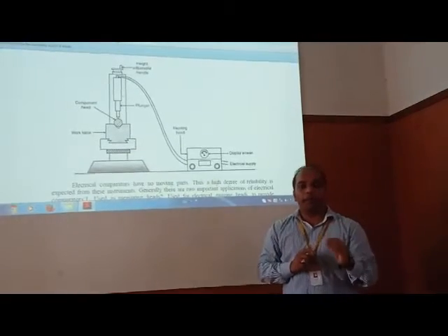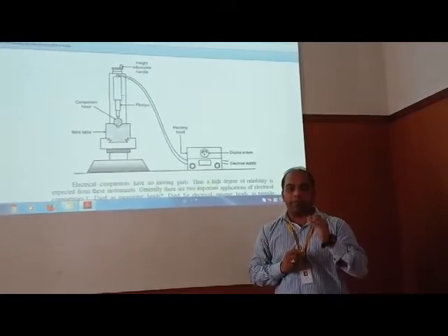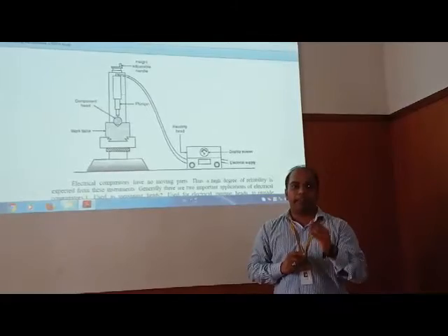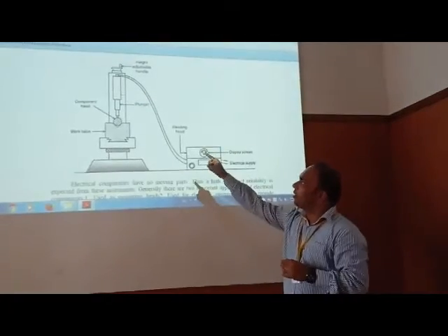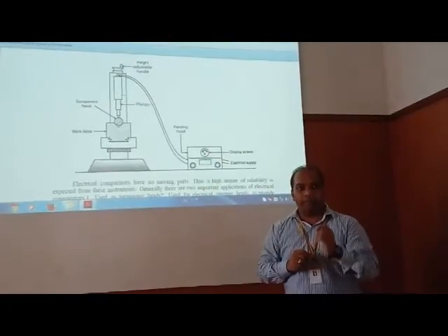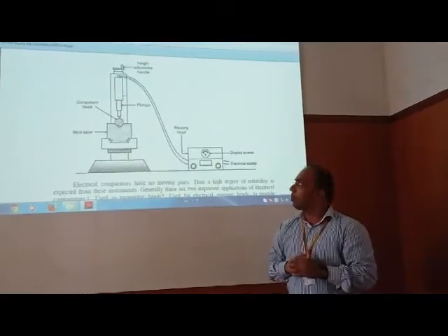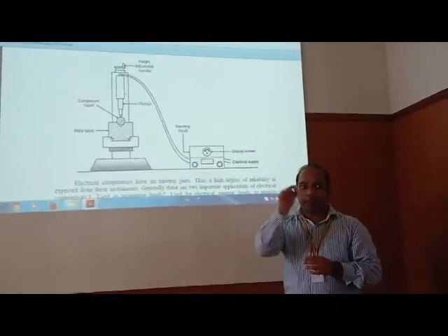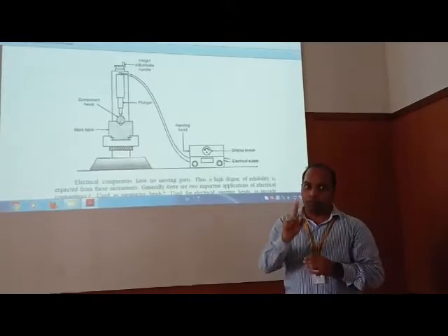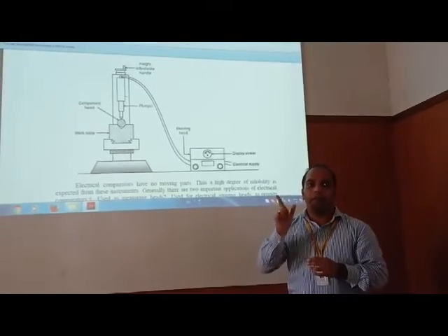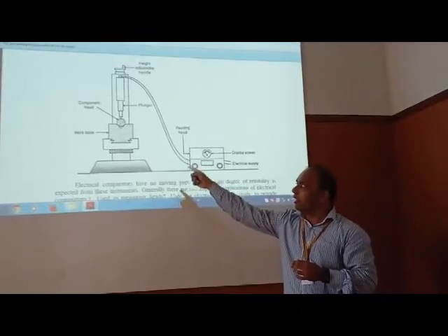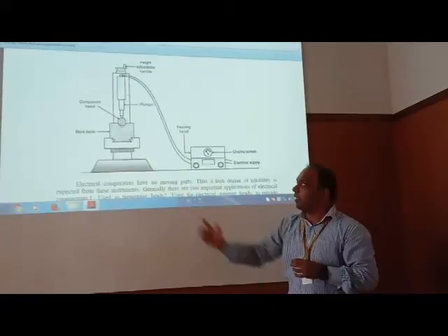Of course, the plunger is the most integral part of the comparator. The plunger is in touch with the connecting head of the component. The component is of cylindrical dimensions, so by the adjustment of the structure it is connected to the work table, you can clearly see.